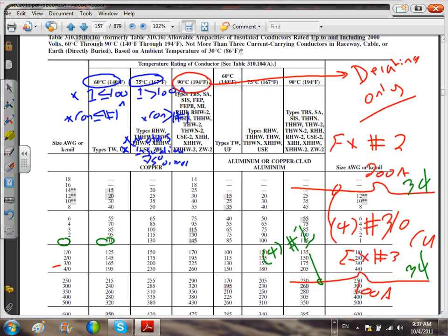Okay, so I have a 100 amp overcurrent protection device. I need to match it. So number 1 can get you 110, you're good to go. Copper, we're doing the copper. Okay, so before I leave here, I want to make sure everybody also knows the small conductor rule.